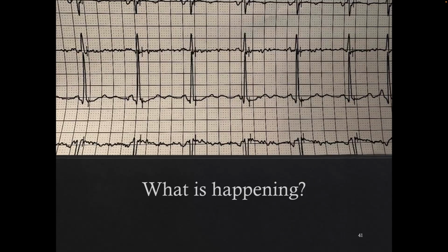I got an x-ray. The lead looked like it's still okay. I had the company check, because I'm here this morning. I have the company checking to see if they can change the polarity or the configuration on the device. I called the nurse last night. When I changed the sensitivity, there was no further episodes of this where it tried to pace. So this is an example of undersensing, right? So I had to make it more sensitive. So I had to make the number that was set at 2.8, and I brought it down to 0.9 millivolts, and that was on the implantable device. But this is something that you can see as well, whether it's through a temporary pacer or your permanently implanted transvenous system.